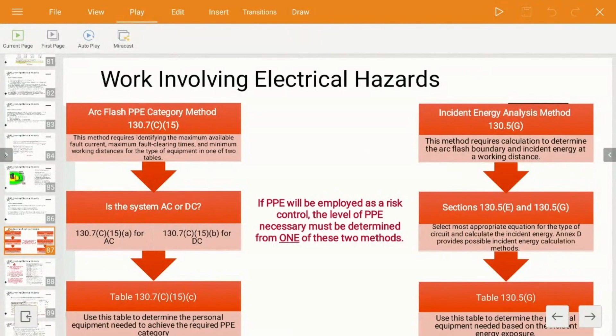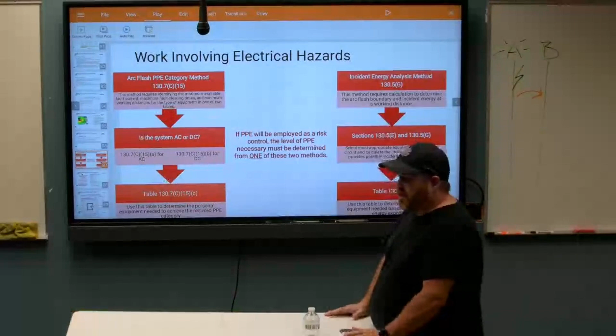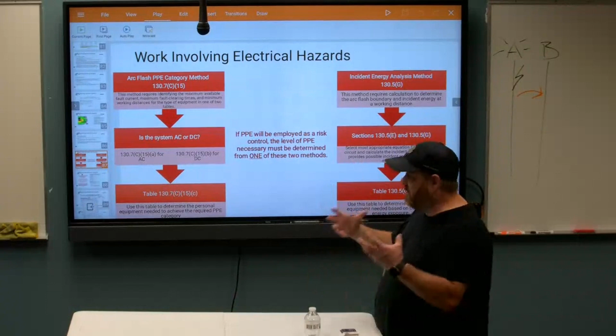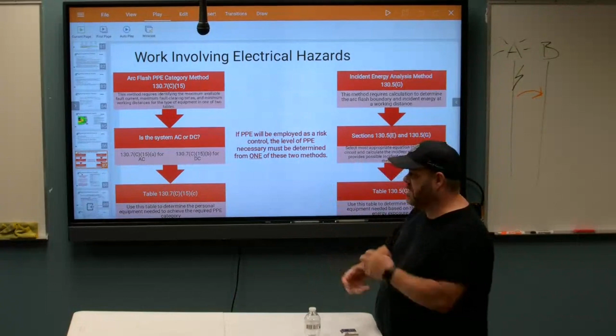One method is there's a table we can look at in the 70E, and it'll give us the level of arc flash PPE we have to wear and our arc flash boundary. The other method is what's called an analysis method, where we hire an engineer. He looks at the entire system, does a study. He puts a label on each piece of equipment, and that label tells us how bad the arc flash is going to be and what kind of PPE we have to wear at minimum. Does that make sense?